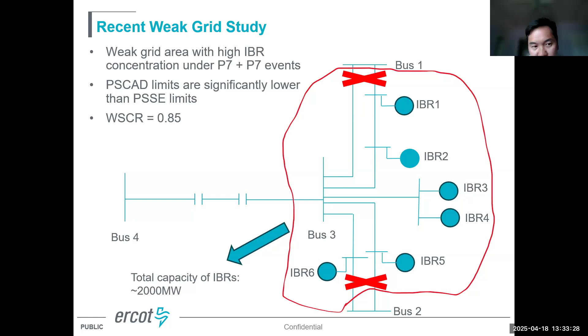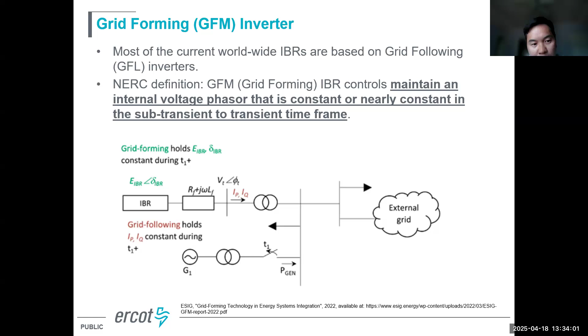This is the SSO event. We have, I believe, probably 20 to 30 hertz oscillation. And again, as I said, it's not really related to series compensation. So to overcome this kind of weak grid issue, we propose grid forming batteries. I think there has already been a lot of discussion about grid forming, so I will just quickly go through this. In theory, grid forming basically tries to maintain the internal voltage phasor, in magnitude and also angle, constant or nearly constant in the sub-transient to transient time frame.